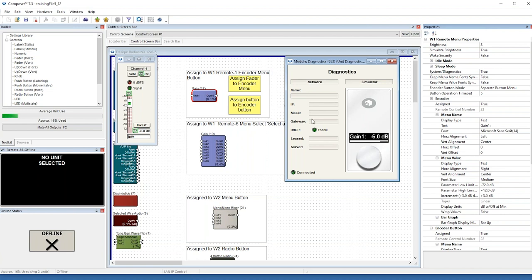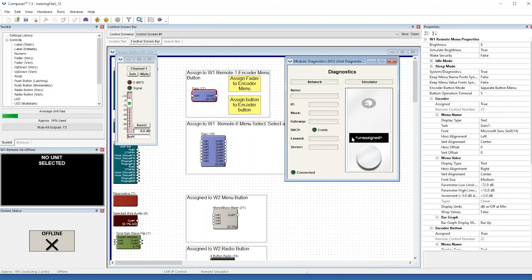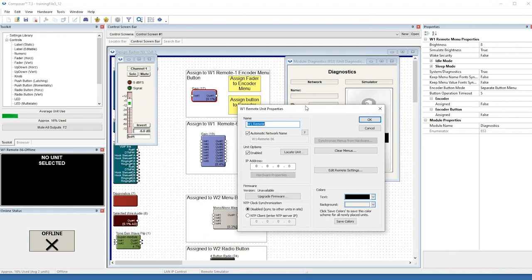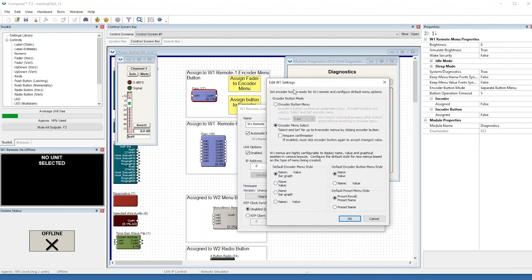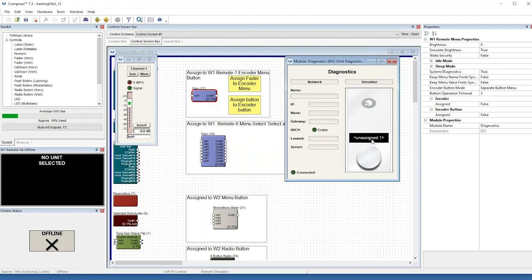Let's try setting up the W1 for select and set — so let's clear the remote settings and get this back to state as if it were brand new and unassigned. I'm going to right-click on the W1, choose Unit Properties, then Edit Remote Settings, and choose encoder menu select instead of the default encoder button menu. I'll leave Require Confirmation unchecked in this demonstration. Note that the timeout option is available for encoder button menu only, and Require Confirmation is available for encoder menu select only.